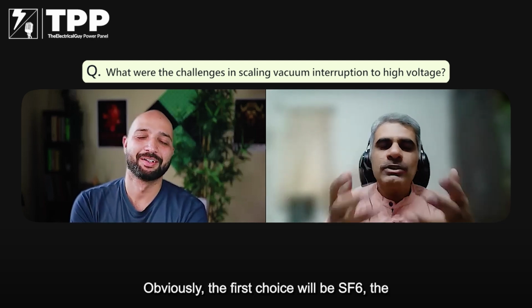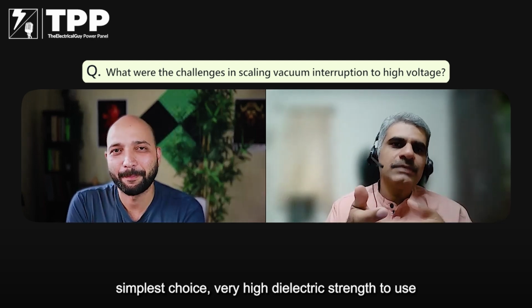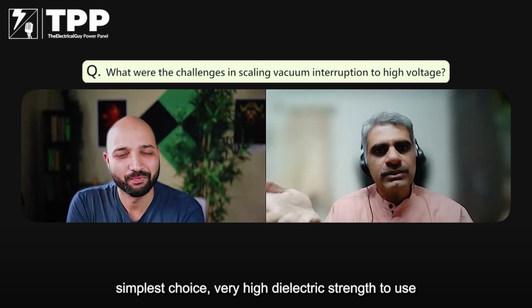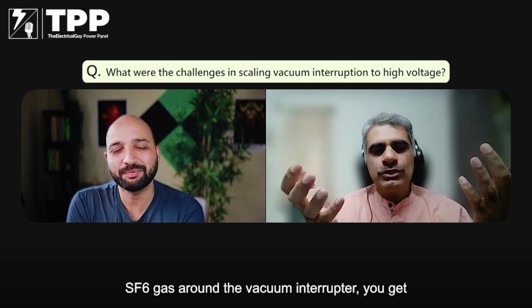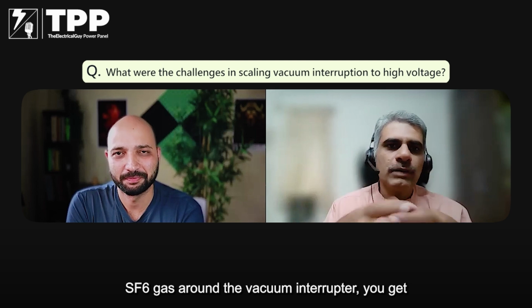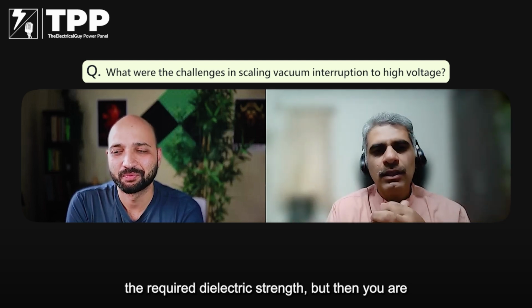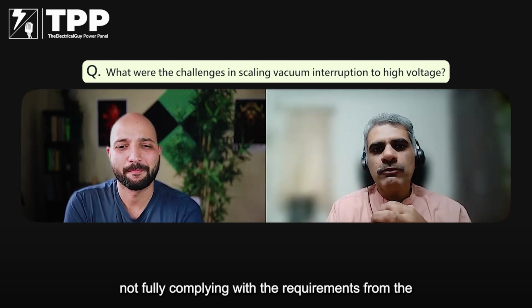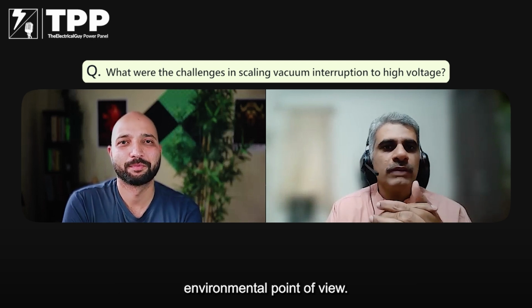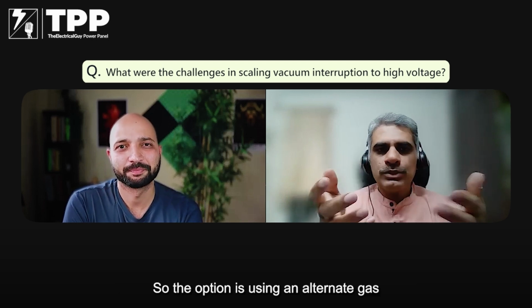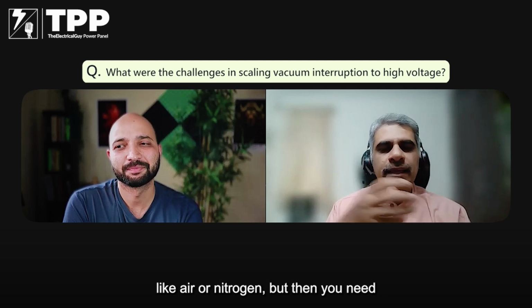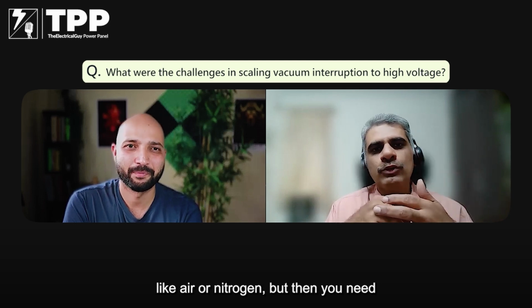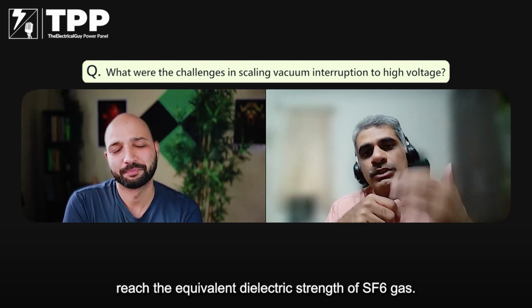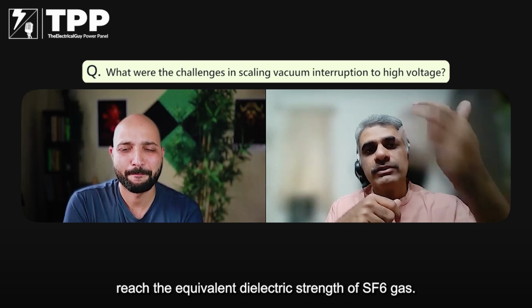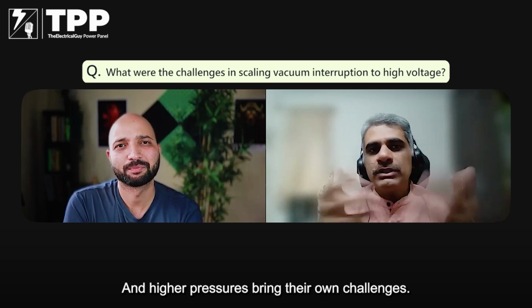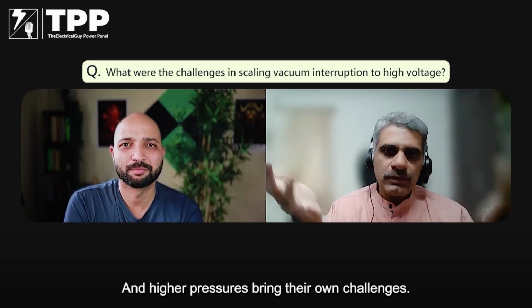True. Obviously, the first choice will be SF6, the simplest choice, very high dielectric strength to use SF6 gas around the vacuum interrupter. You get the required dielectric strength, but then you are not fully complying with the requirements from the environmental point of view. So the option is using an alternate gas like air or nitrogen, but then you need to use it at much higher pressures to reach the equivalent dielectric strength of the SF6 gas. And higher pressures bring their own challenges.